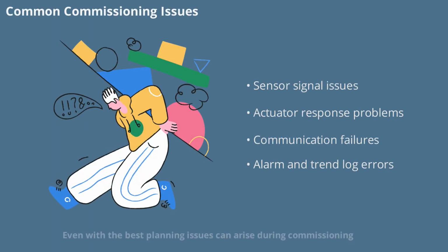Even with the best planning, issues can arise during commissioning. Common problems include no signal from sensors due to wiring errors, actuators not responding because of incorrect voltage, and communication failures from duplicate device IDs. Alarms might not trigger if logic is faulty, and trend logs may not record if points are offline. Network timeouts can result from loose cables or incorrect settings. Identifying and addressing these issues early is key to a smooth handover.